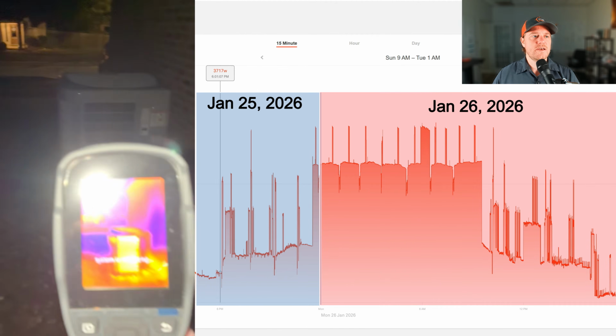Then shortly after, we see the heat strips come on, where we see a 10,000 watt jump. And I'm running 10 kW heat strips, so it all makes sense. And you can see it cycling a couple of times. Actually, this section here is Sunday. And right here at 6:30 is where I'm getting the B-roll film from.